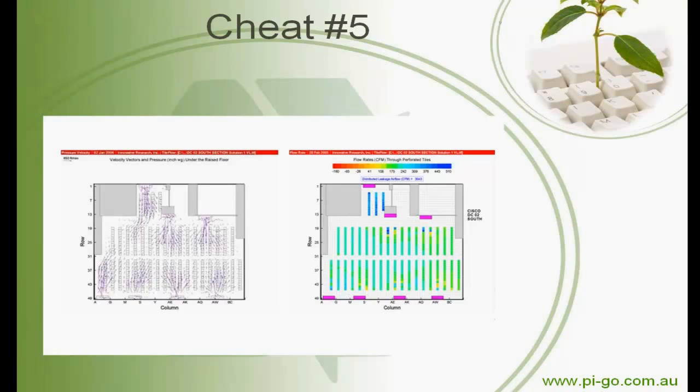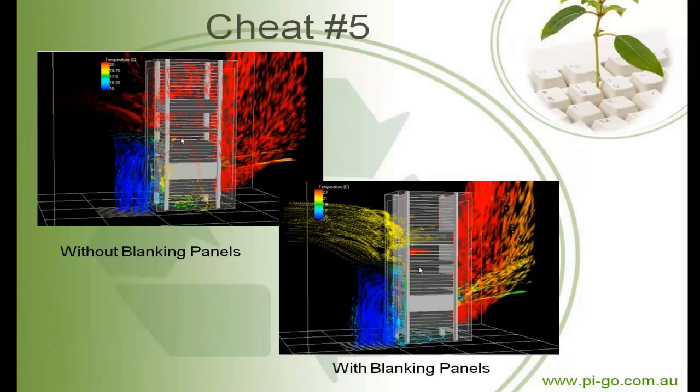One of the other areas that is very simple to approach is, of course, using blanking panels in the right place, and doors and things on racks, and making sure that they're put into place. There's lots of other small things that they can do, but I'm trying to show you here with some graphics that you can achieve some really phenomenal results if you get an expert in to go through your data center or server room and quickly do a study. The investment required for their time pays back most of the time very quickly.